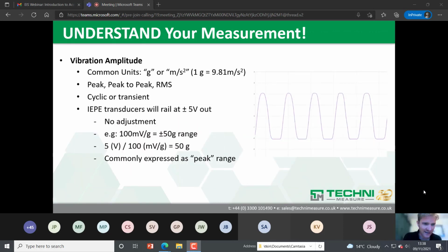Remember a very important fact with using IEPE transducers: they will rail at plus or minus 5 volts output, and there's no adjustment on those. So you must make sure you choose your accelerometer with enough headroom in the range that you will be able to get your measurement. Otherwise, you'll see something like this in your data where you flatline the measurement and you're missing out the peaks, which is a really bad situation to be in. Very quick calculation: 100 millivolt per G sensitivity on an accelerometer will give you a 50 G range. That is the 5 volts of the IEPE circuit divided by the 100 millivolt per G to give you a 50 G range. And that is a peak range. So your peak to peak will actually be 100 G for that, or plus or minus 50.